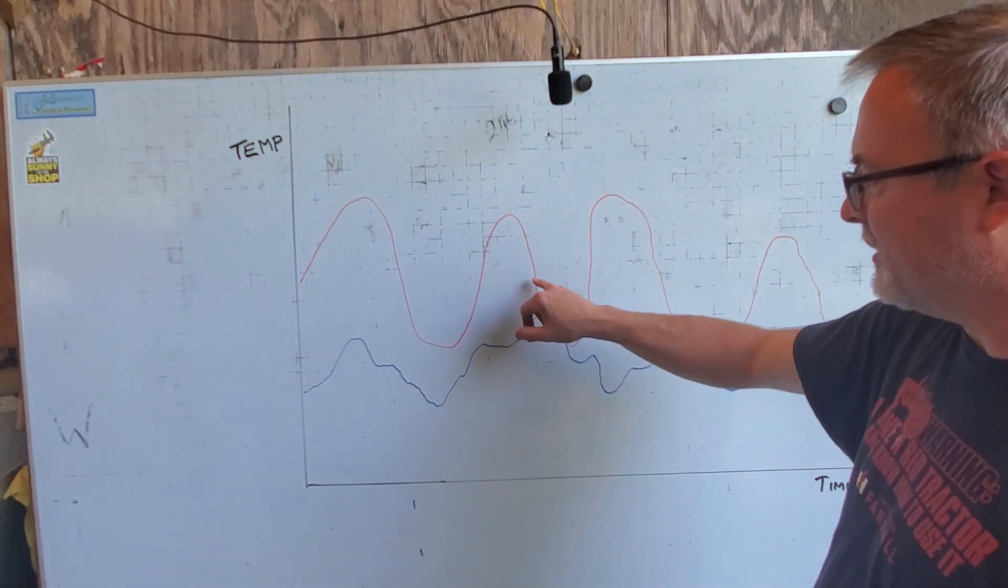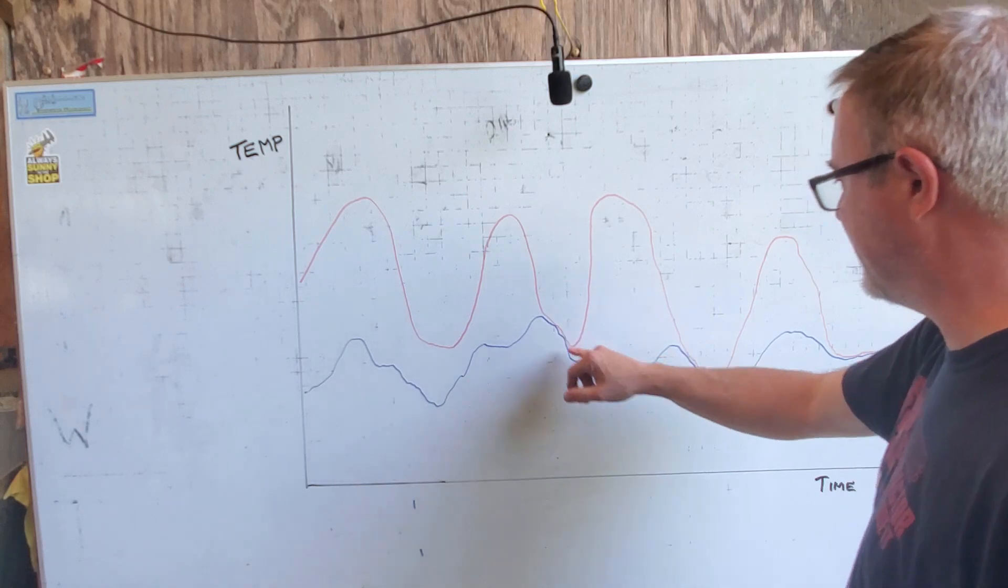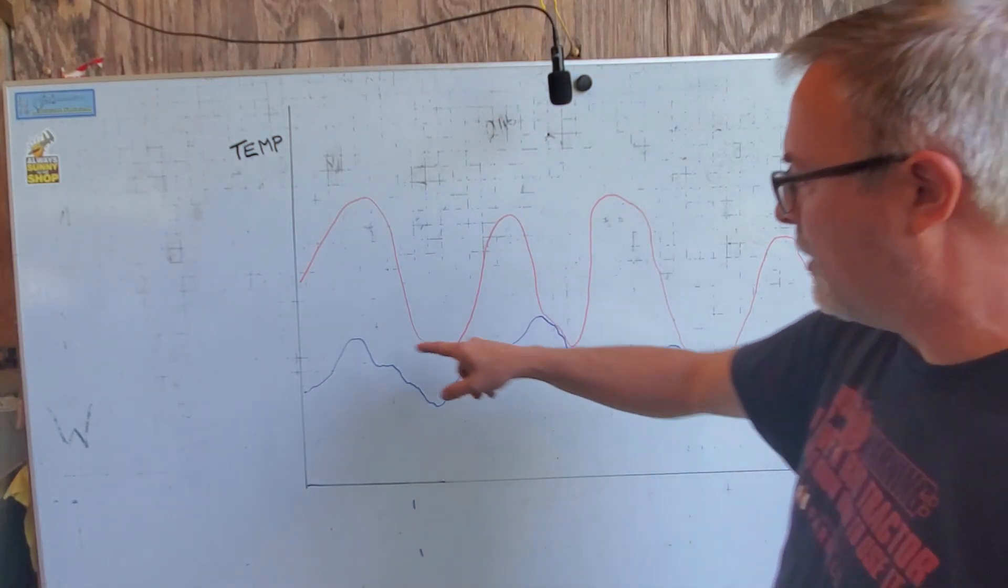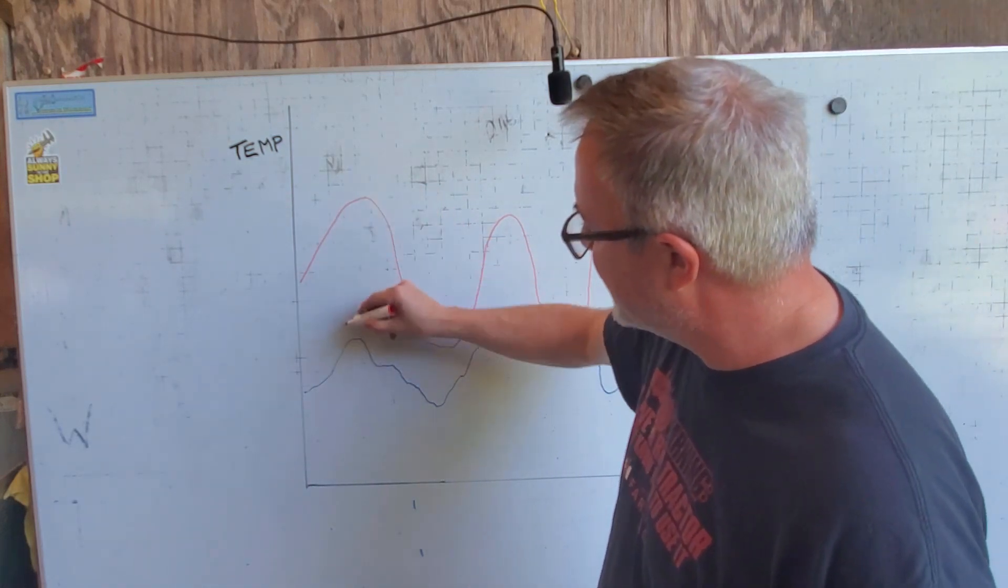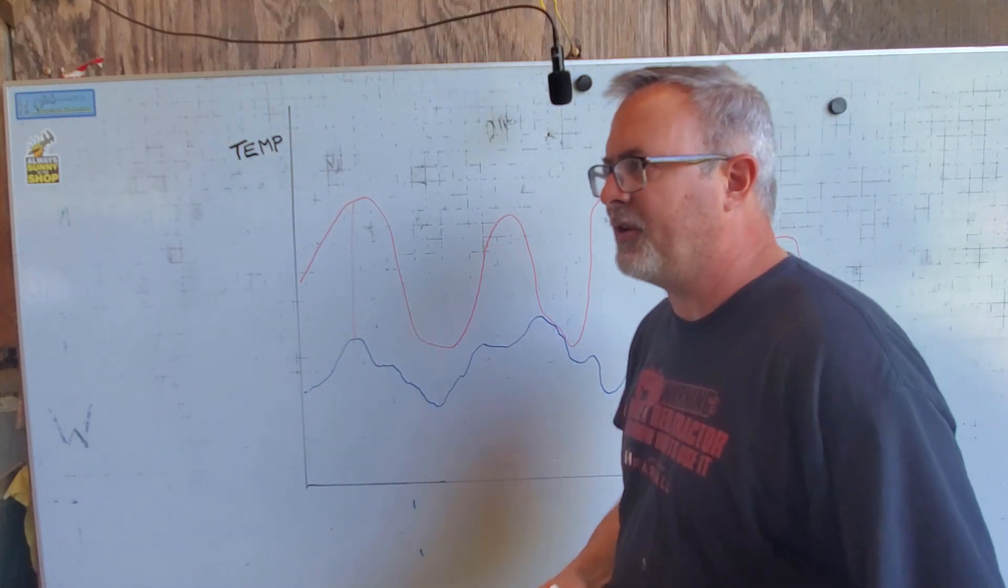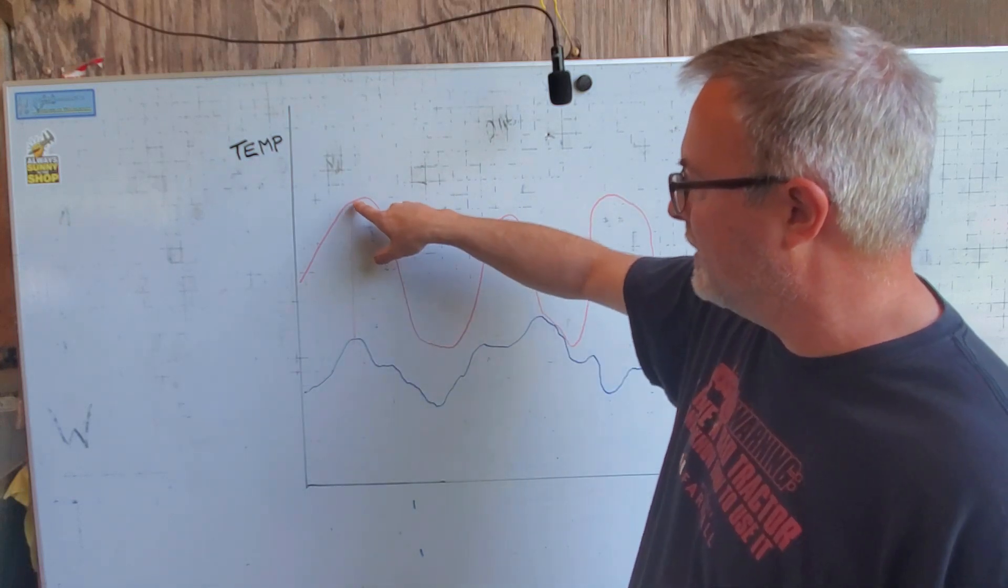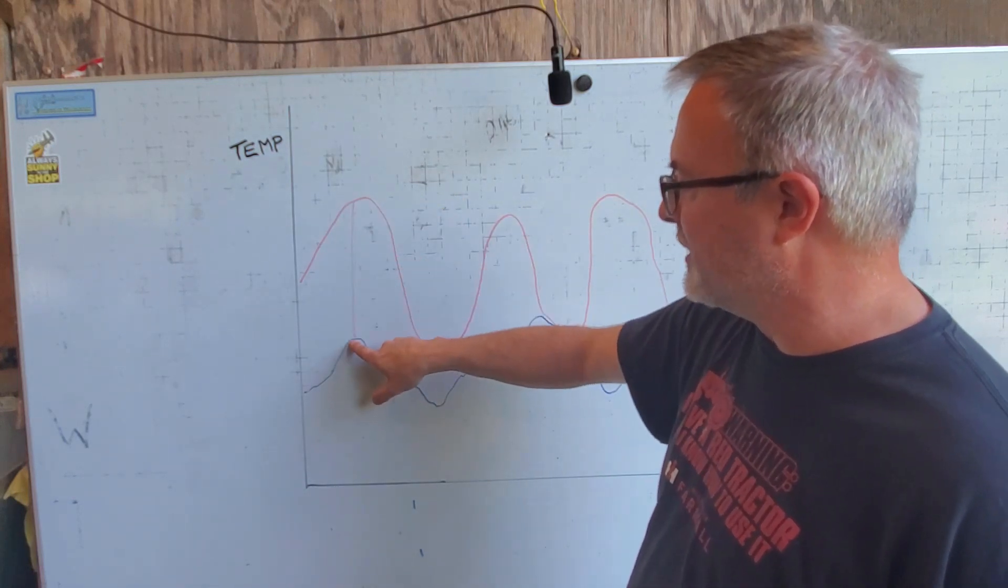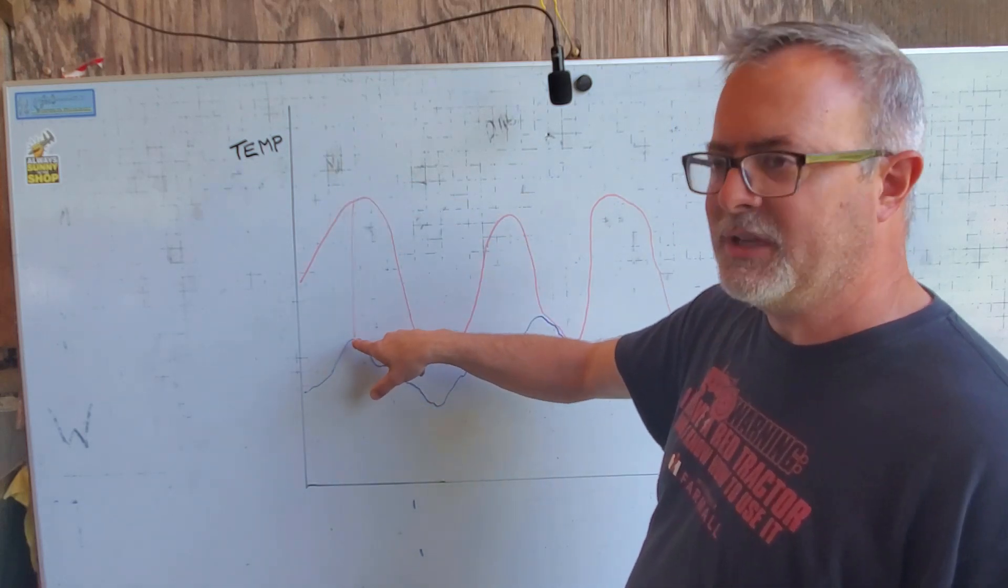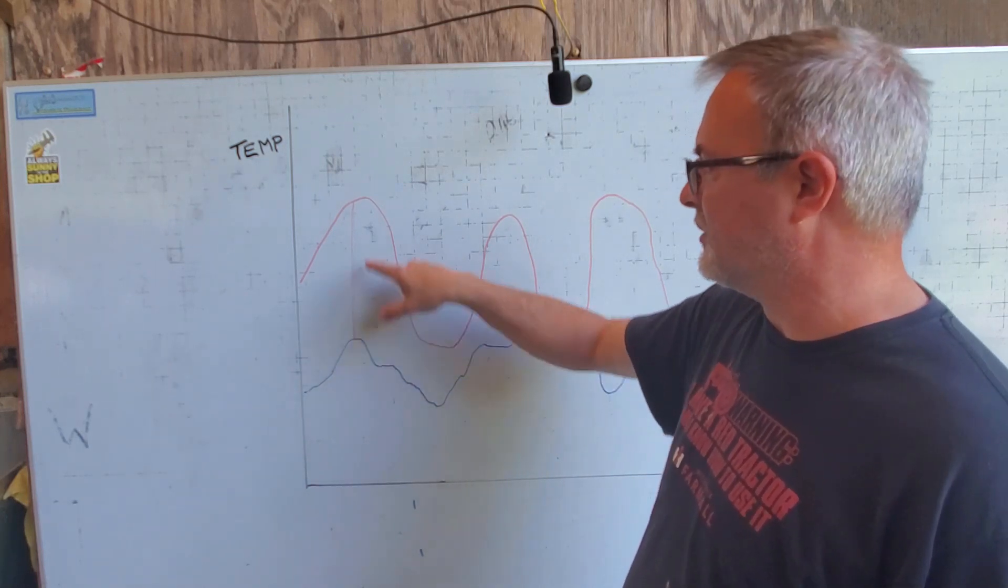Because what happens is when the temperature and the dew point are at the same level, the air is 100% saturated. So this temperature line will never go below the dew point line. Now, what's this gap in here? This gap in here is a visual indicator of the relative humidity. It's the amount of moisture that the air can hold at any given temperature.